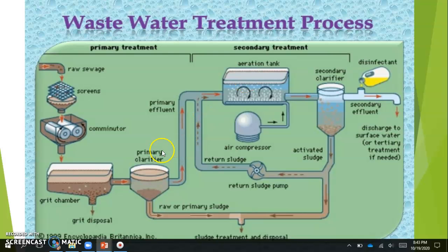Oh, so the initial settling tank was right here. So the settling tank, most of the big solids are settled out. Then you push it forward to the aeration tank where we have the oxygen that's given to the bacteria, who will then eat a lot of the waste. Then it's pushed to the secondary clarifier, so another tank where any remaining solids can settle out. Then it will be disinfected via UV light and chlorine.